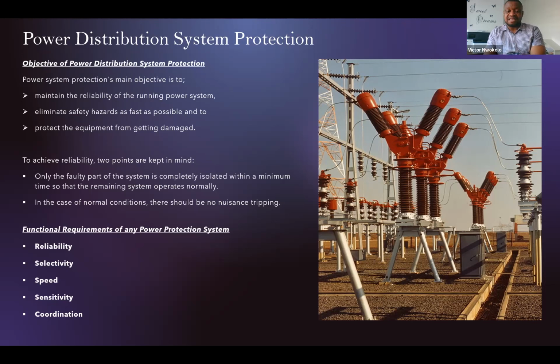Then the final thing there is the coordination. Coordination is basically taking all four of the earlier requirements into account: the reliability, selectivity, speed, and sensitivity. So when all of these are correctly designed and operating in the correct manner, then the system is correctly coordinated. And it also allows us to operate a system correctly. Coordination also looks at the equipment itself, making sure that the equipment doesn't get damaged. Like when you put in the speed, in your coordination, you take the speed of the protection system into account.